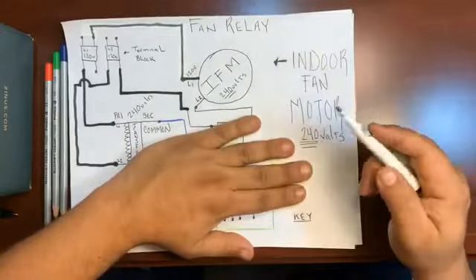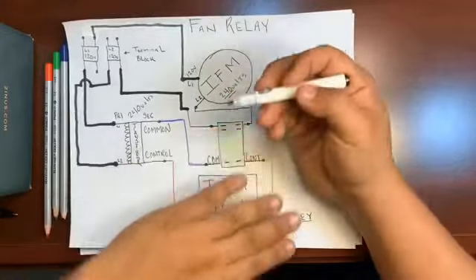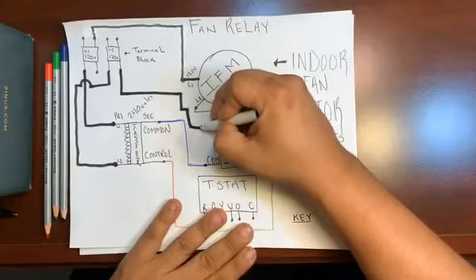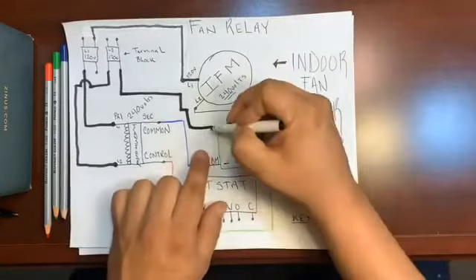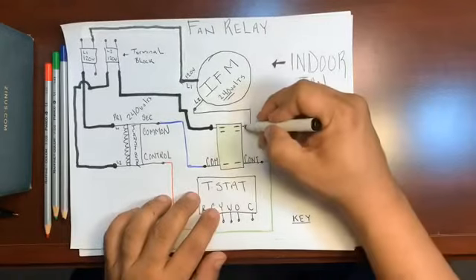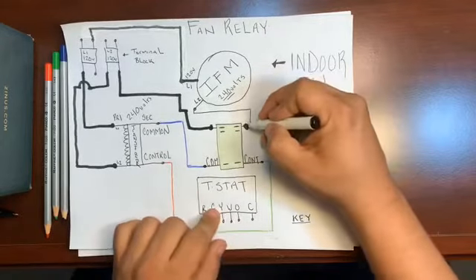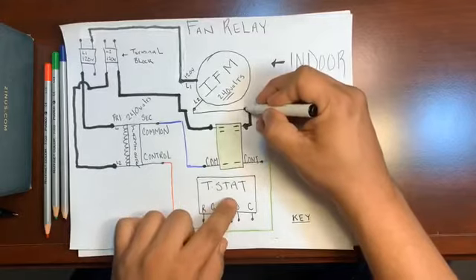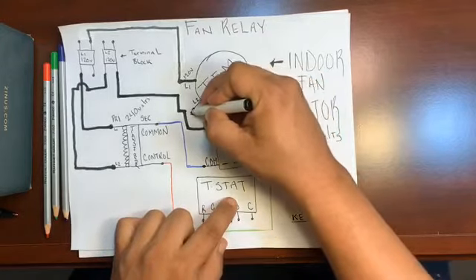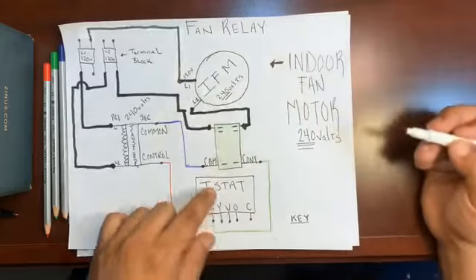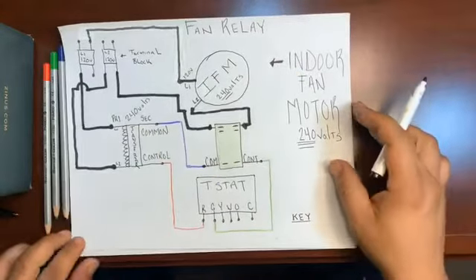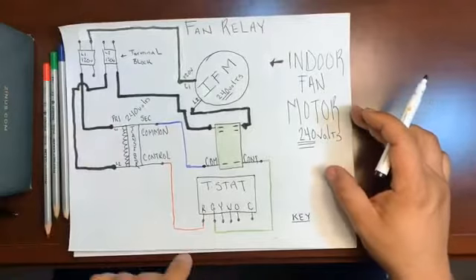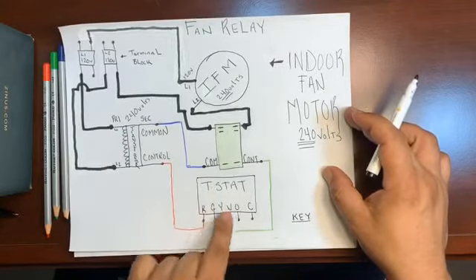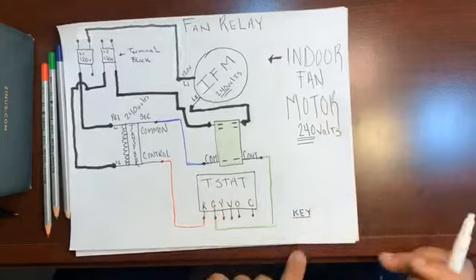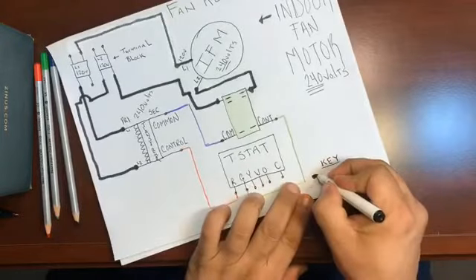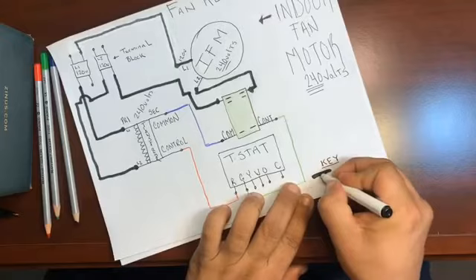How do we give the thermostat control? Well, let's take this leg, and at the very last second, let's bring it down, feed it into a fan relay that we control with low voltage. So when the thermostat says we want fan motor inside, then we'll close the circuit and bring the 240 volts back. Complete the whole 240 to the fan motor. Now we can control the indoor fan motor with just 24 volts that's going through this thermostat from the red to the green. We'll do our key. Let's go ahead and get a nice thick line on here. That'll do it.